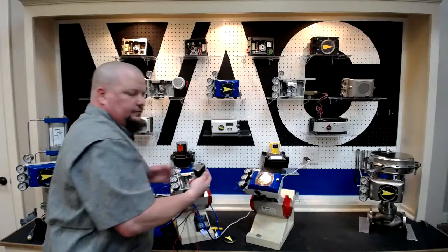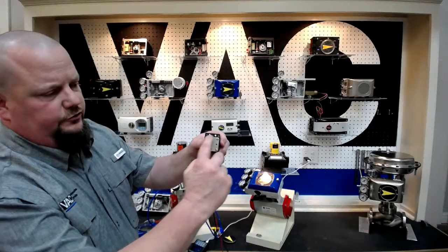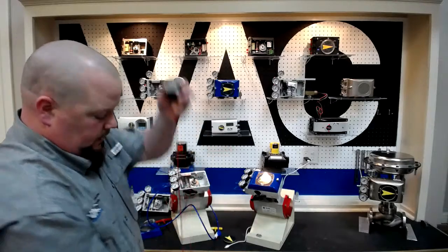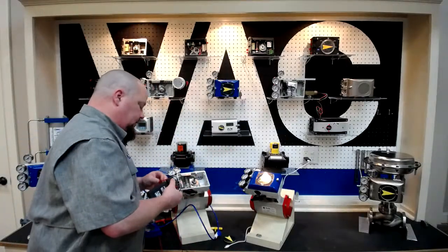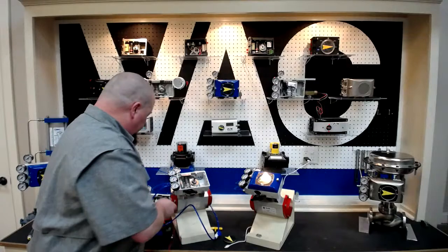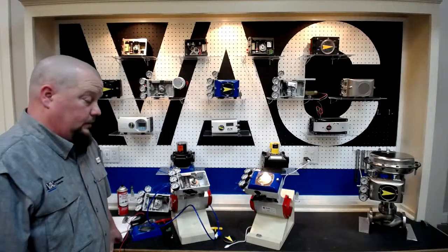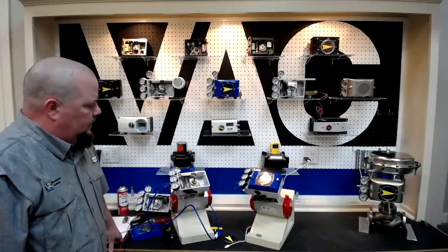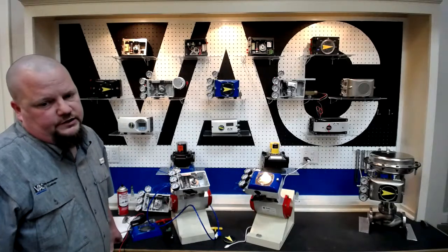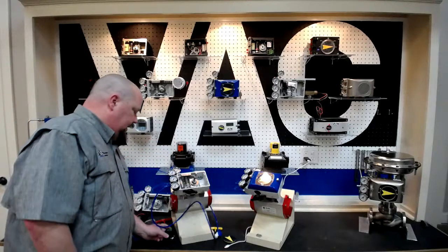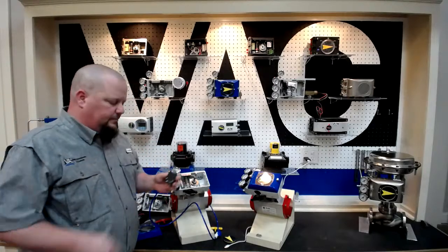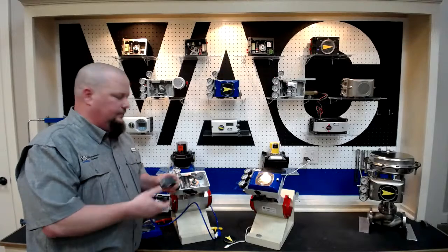If you get a bunch of oil, there are 2 filters in this area here. And if you have a lot of issues with oil and dirt, those will become clogged and discolored and be brown, or any number of colors. That'll be the first issue that we look for. And that's a dead giveaway that the I2P has been full of oil and it's not functioning.